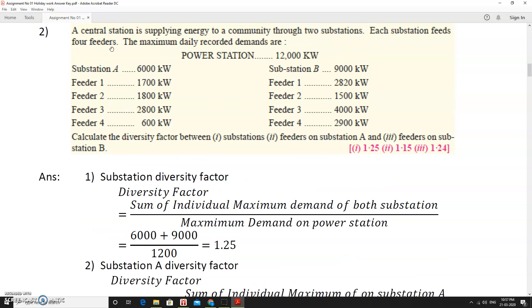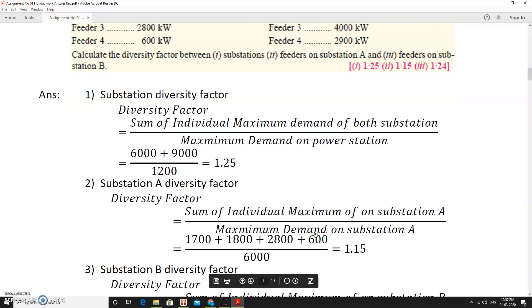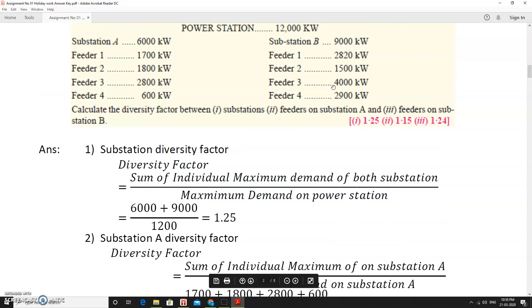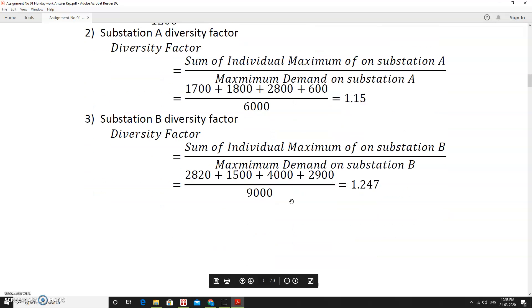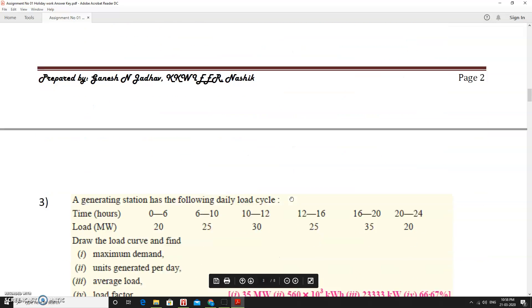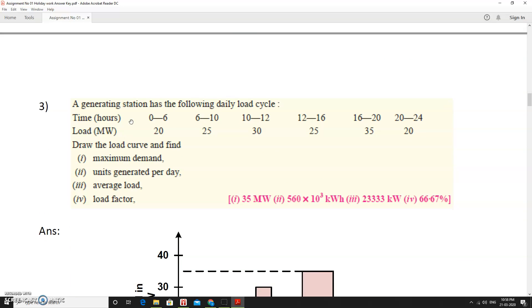For substation A, the sum of individual feeder maximum demands is 1,700 + 1,800 + 2,800 + 600, divided by 6,000, giving a diversity factor of 1.15. Similarly for substation B, the sum is 2,820 + 1,500 + 4,000 + 2,900, divided by 9,000, giving the diversity factor for substation B.